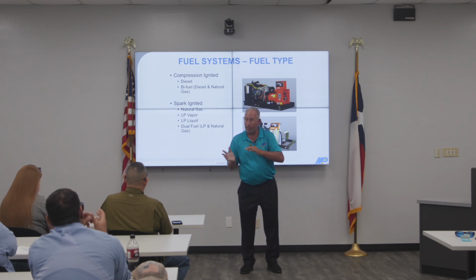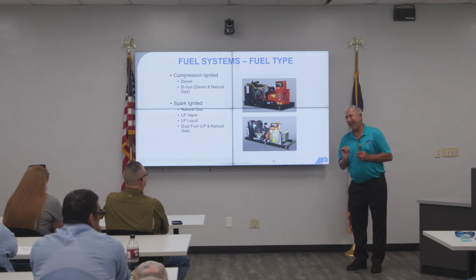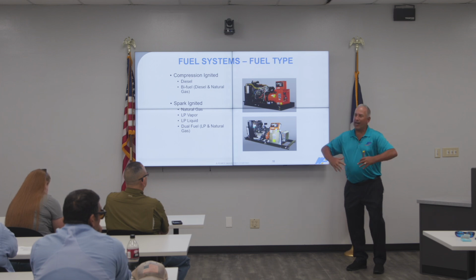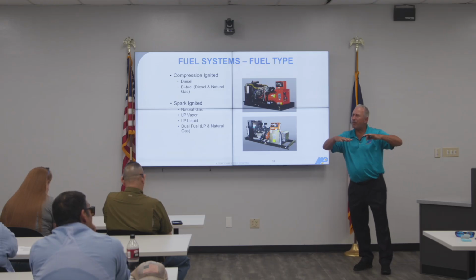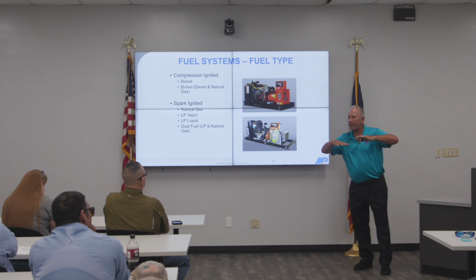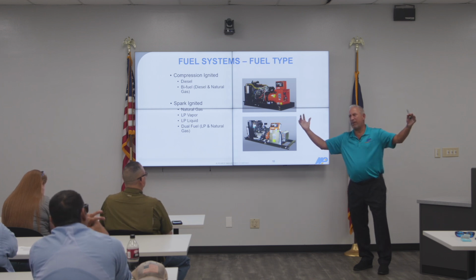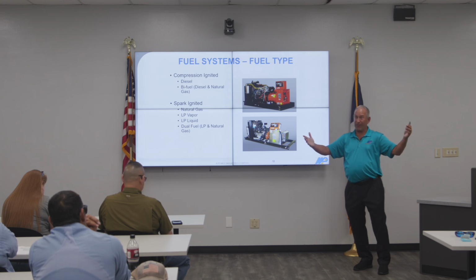That's a dual fuel. Now, the challenge that you have with propane is propane gives off a lot of BTUs. So propane is hot, and to combat the heat, you've got to put a lot of block there. And what happens is, as you start getting bigger, the cost of the block pushes the generator pricing out of the market, right? So about 150 kW is generally where you stop with propane. Just because you go any larger, the block becomes so big, it's so expensive, and you've got yourself a 200 kW generator that you've paid way too much money for.